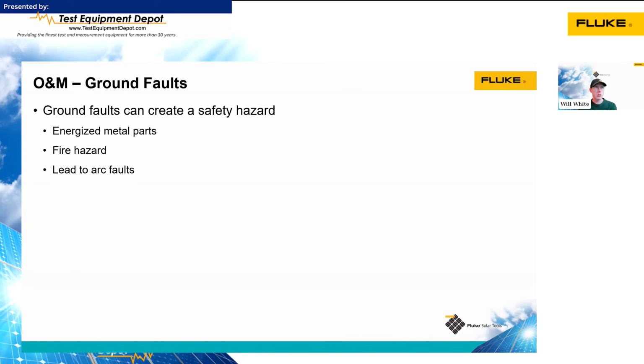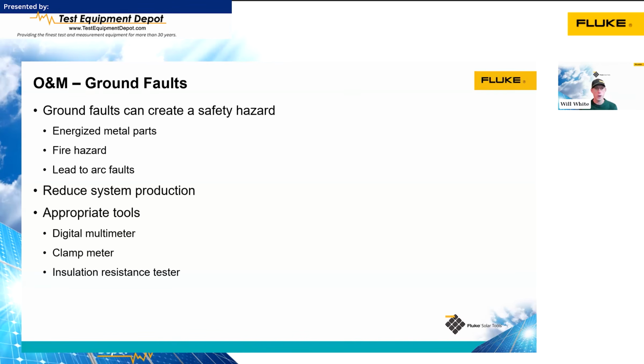Ground faults can be a safety hazard. You could have energized metal equipment. It could be a fire hazard because that fault could be arcing between the conductor and the metal part. It could be a ground fault and an arc fault at the same time. Those arcs can actually lead to sparks, which may set things on fire. I've heard of ground-mounted systems that had so many ground faults that they were sparking and setting the grass on fire, leading to grass fires. It also reduces the system production beyond being just a safety hazard. So we have electrons going to ground, they're not going to my load and creating usable energy.